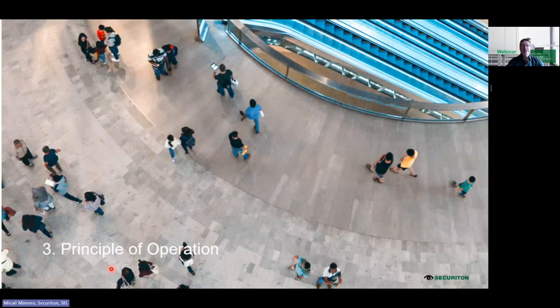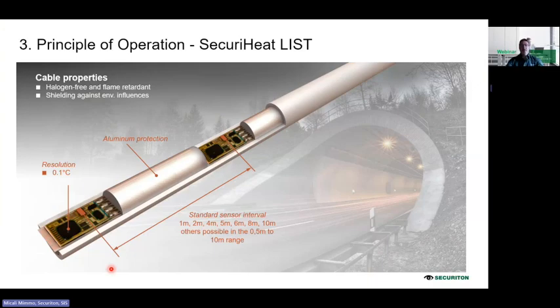Let's see a little bit the principle of operation of this temperature sensor cable. If you can see, it looks like a standard cable, but inside the cable we have different spacements where you can find the temperature sensor. This is embedded in the cable during the production. So you can have different intervals. You have from 1 meter, 2 meters, up to 10 meters.